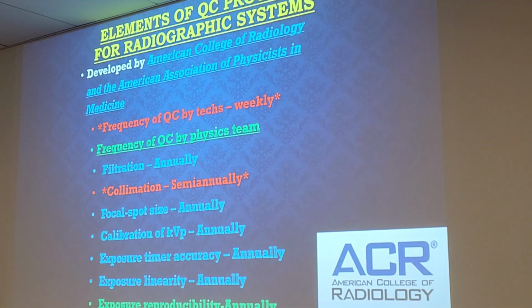One more thing I do want to point out about this calibration. In the video you saw, they mentioned that the calibration took 20 minutes, which is a considerable amount of time. Anytime anyone dropped a cassette on any of the Carestream portables, we would have to go through that 20-minute calibration. I'm not very happy having to do a 20-minute calibration every time I come into the building because every evening someone dropped a cassette from the portables. So please take care of your equipment.